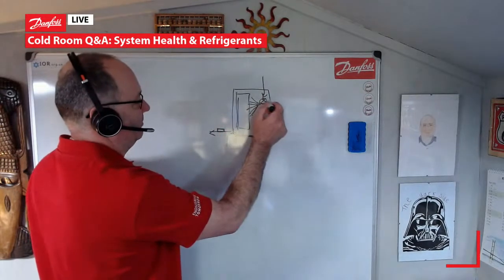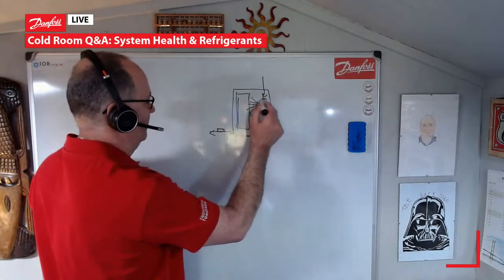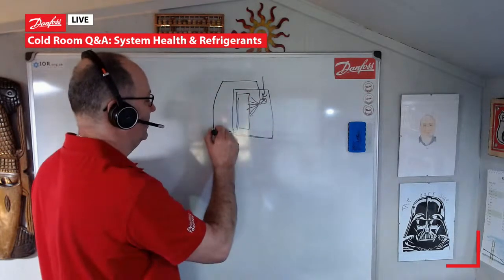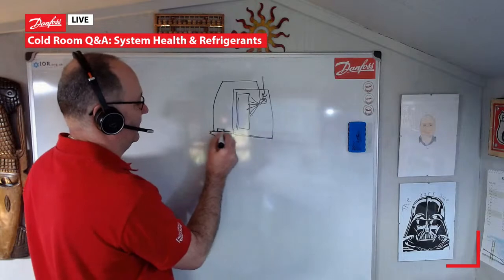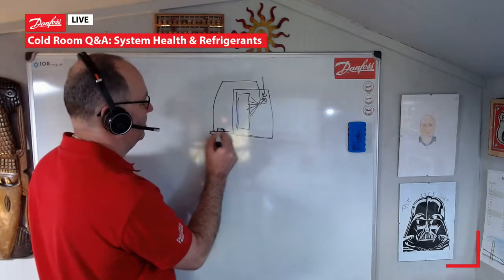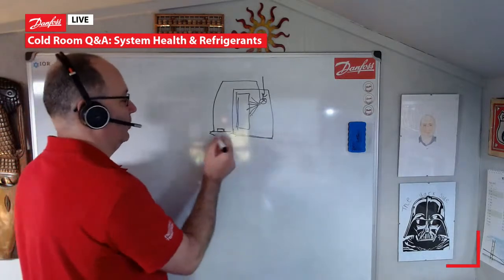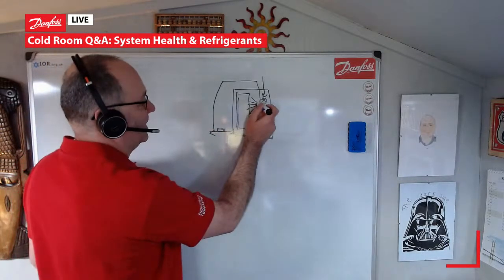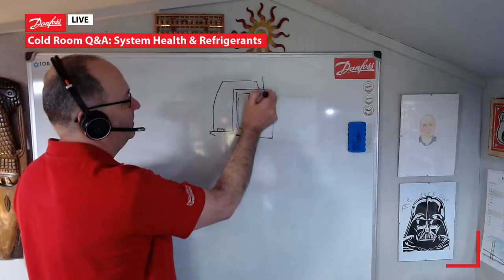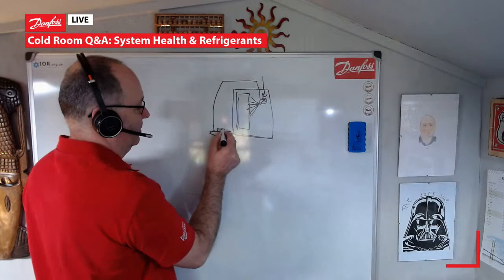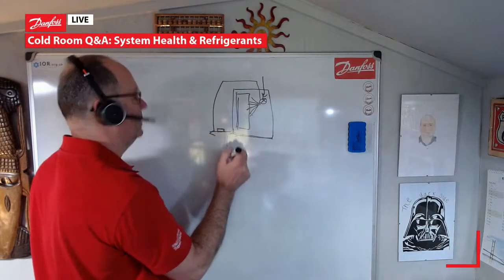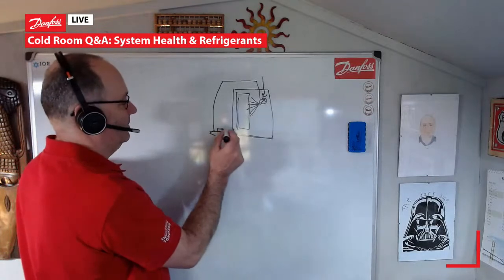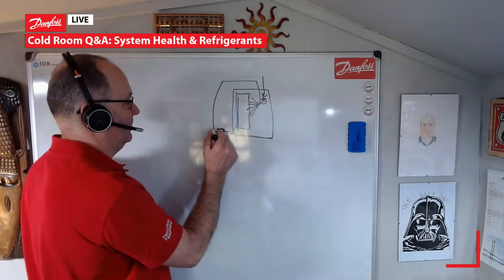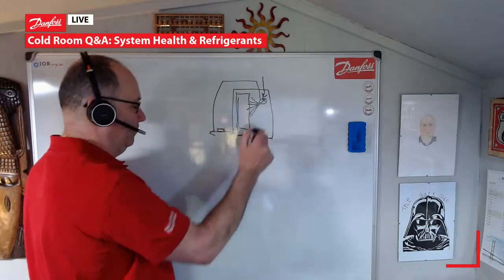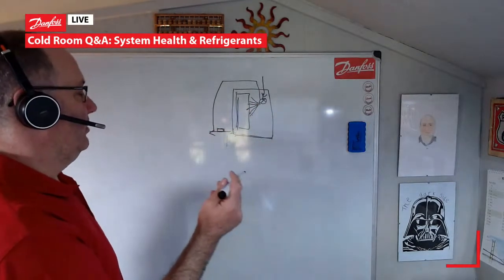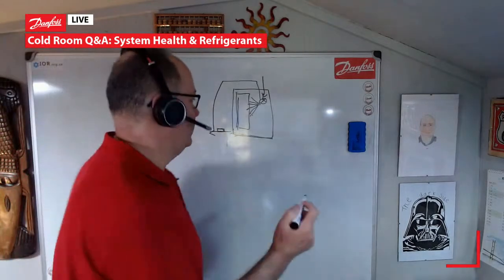If we've got an externally equalized valve, and again, this is for graphical representation only, make sure that the equalization line is after the bulb. We do that basically for one reason and one reason only. If there is any leakage on the equalization line from the valve, it doesn't affect the signal that we're going to pick up on the bulb here. So make sure that is nice and tight, make sure it's insulated, make sure the equalization line is after the bulb. A very basic one, but something that I see a lot on evaporators.